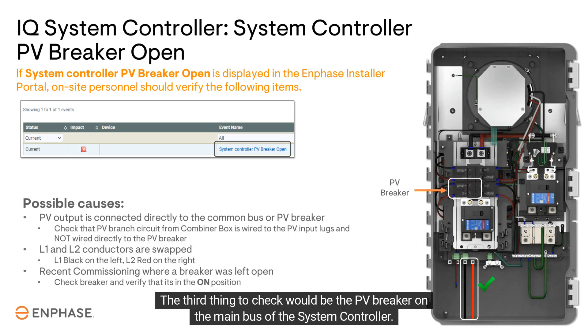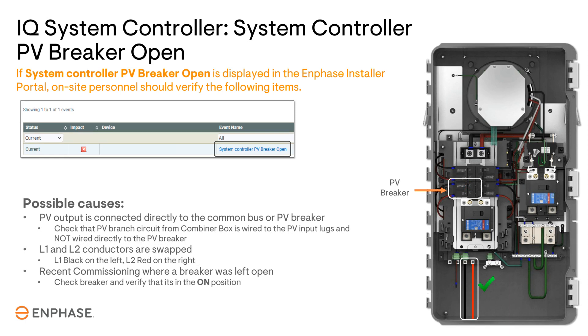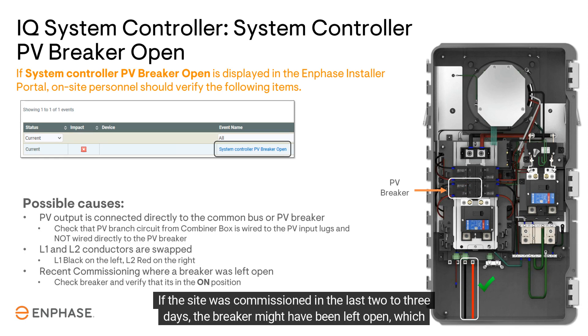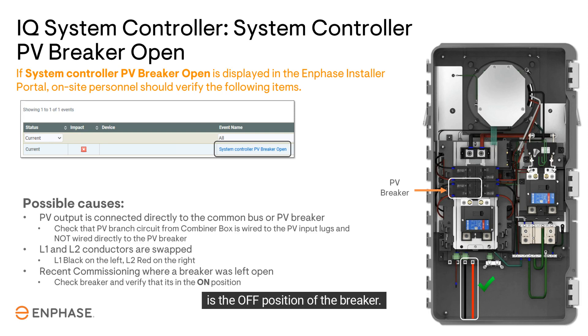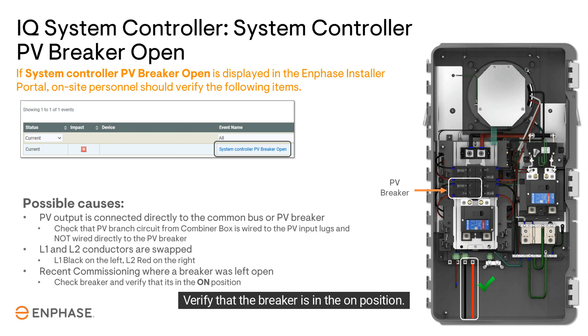The third thing to check would be the PV breaker on the main bus of the system controller. If the site was commissioned in the last two to three days, the breaker might have been left open, which is the off position of the breaker. Verify that the breaker is in the on position.